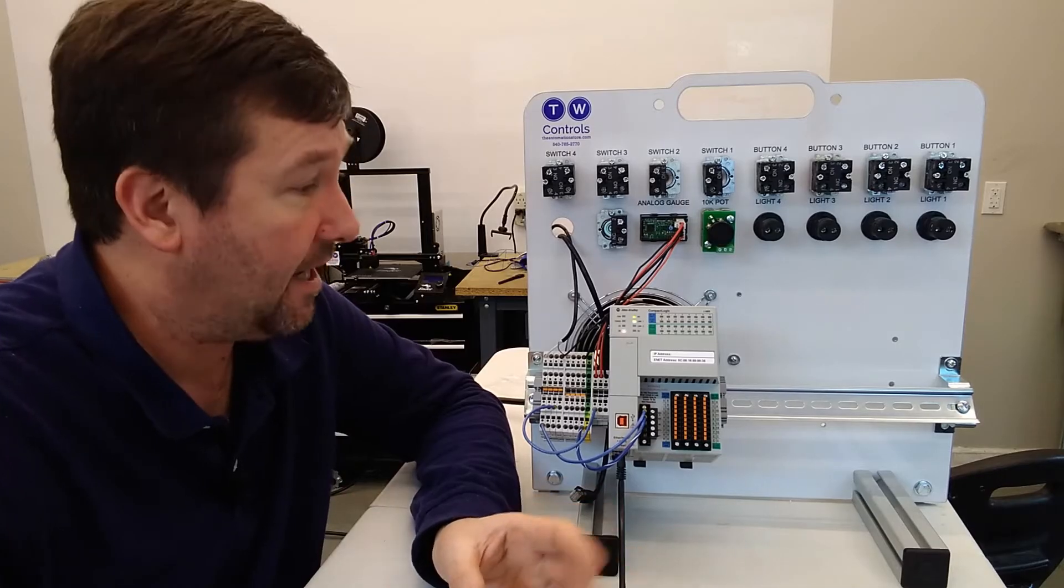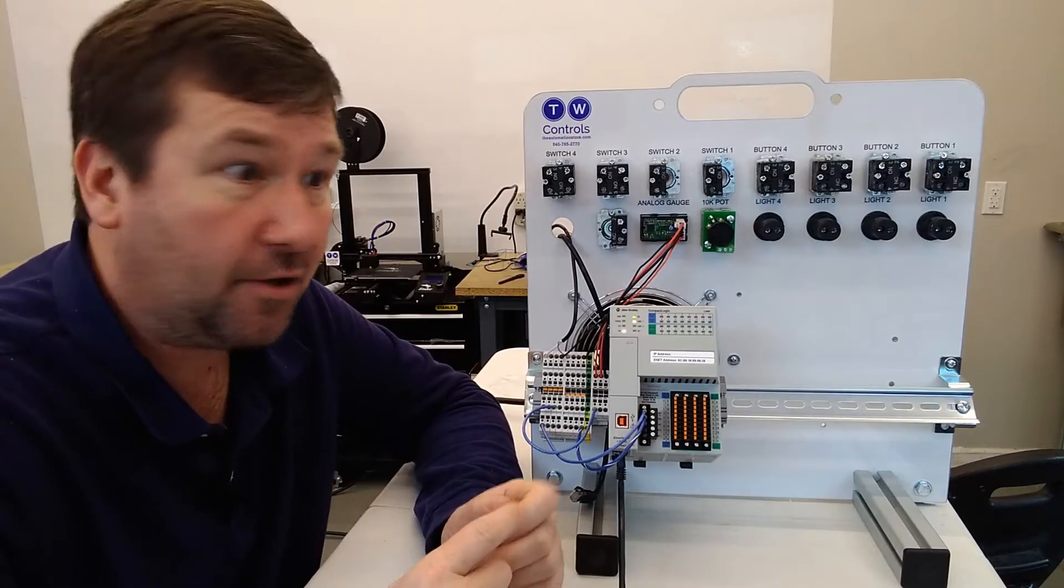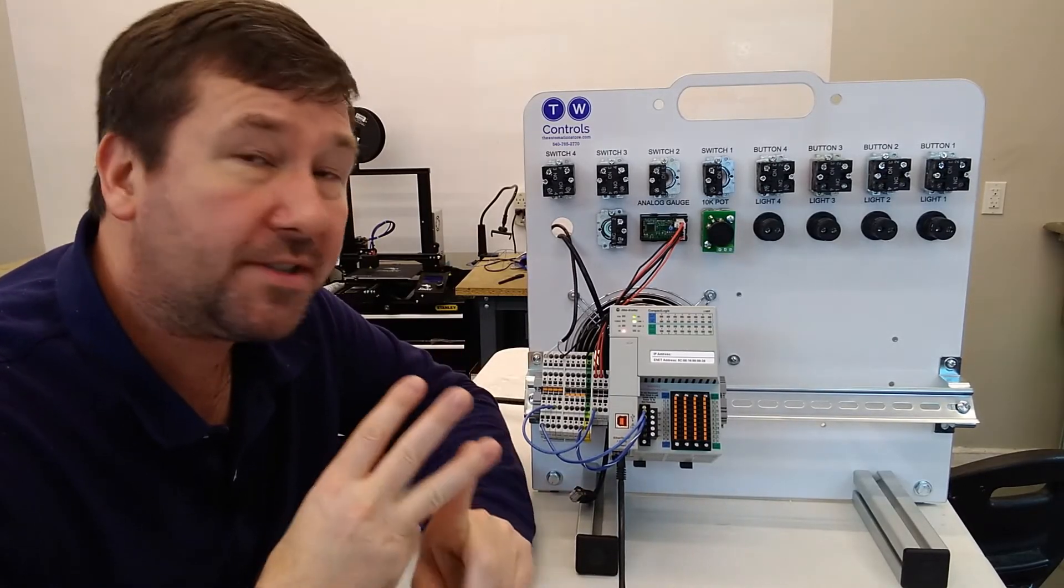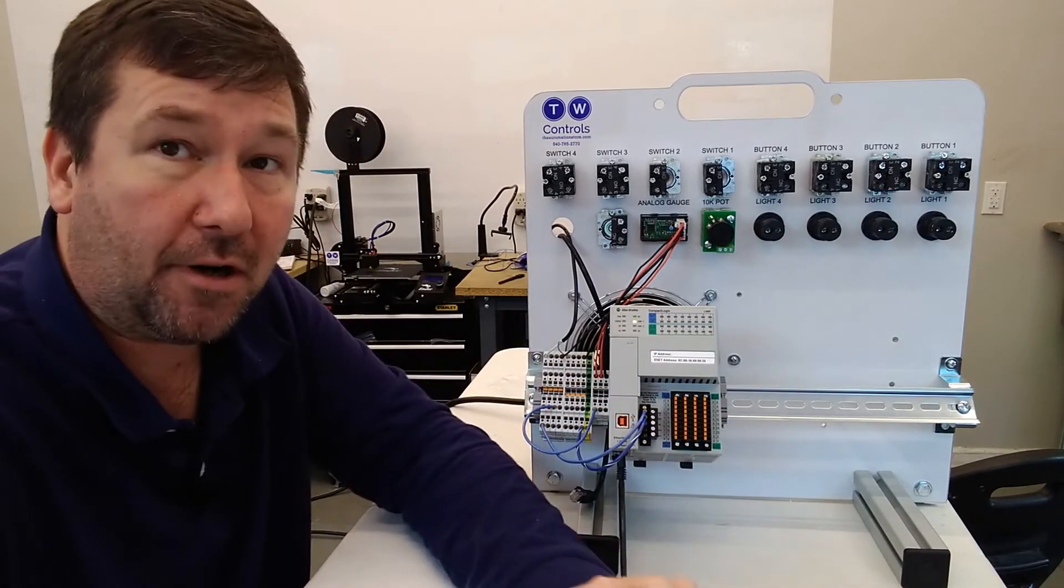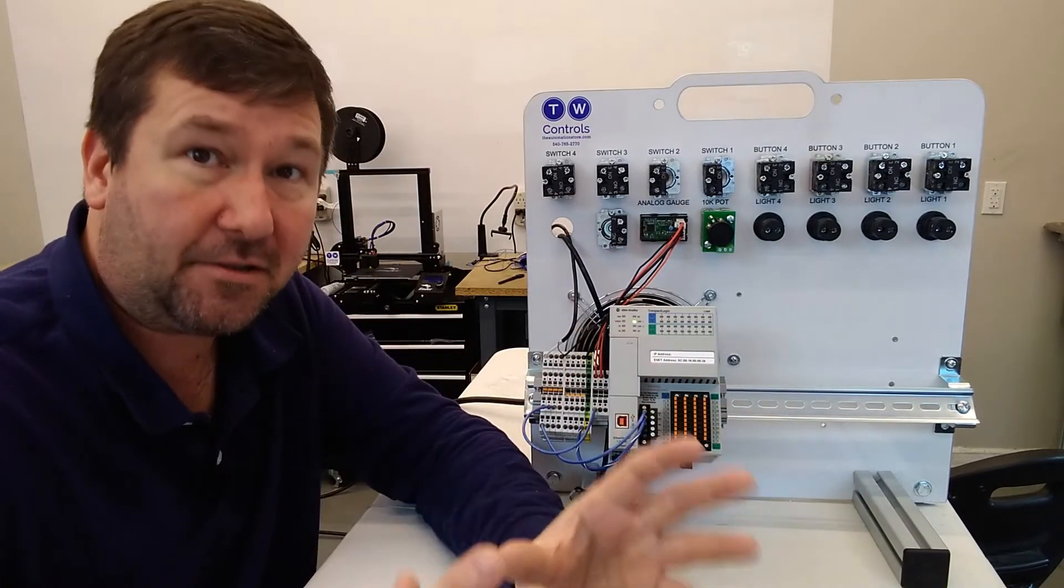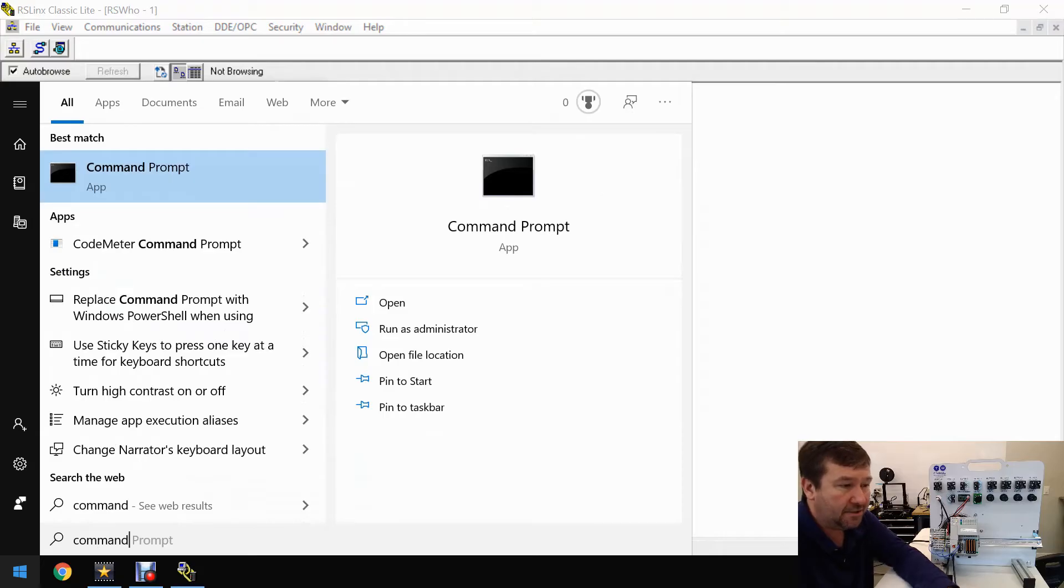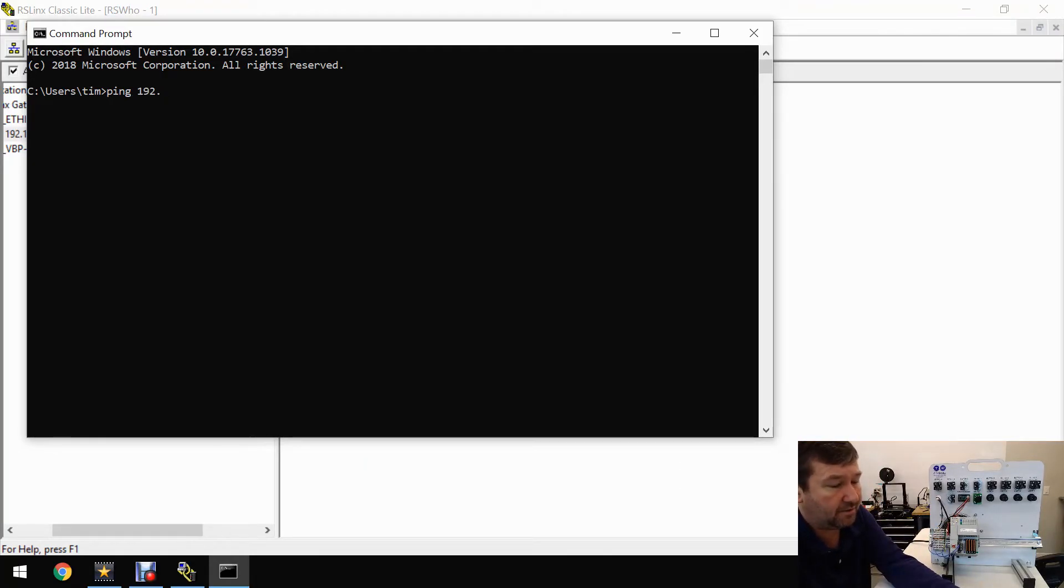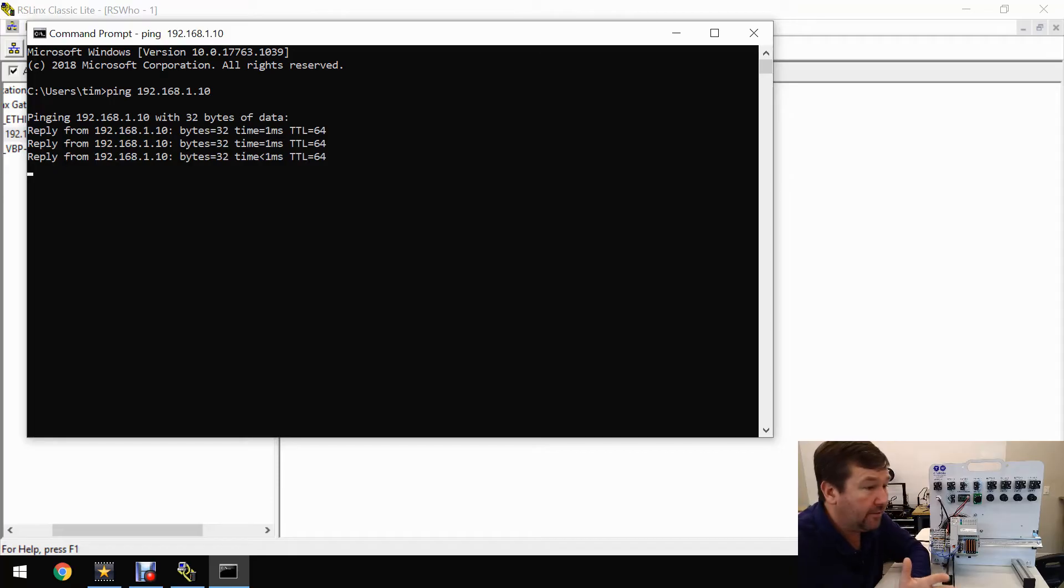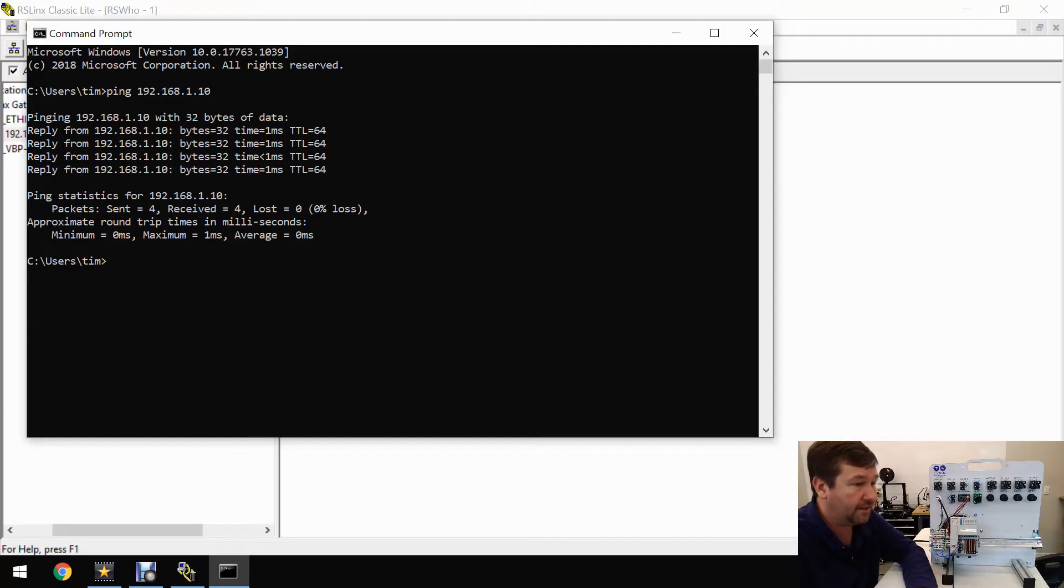Let's say you did those exact steps and your PLC didn't show up. That means one of two things: either your PC can't talk to the PLC, or something is blocking those broadcast packets that lets RSLinx discover PLCs out on the network. Let's tackle whether your PC can talk to the PLC first. The easiest way to do that is through the command prompt. Go to your start menu and type command, and you should see command prompt. Then we're going to type P-I-N-G and the IP address that we believe is in our PLC, which is 192.168.1.10. It's going to give you a lot of info, but the main thing we're looking for is that we are getting replies from it.